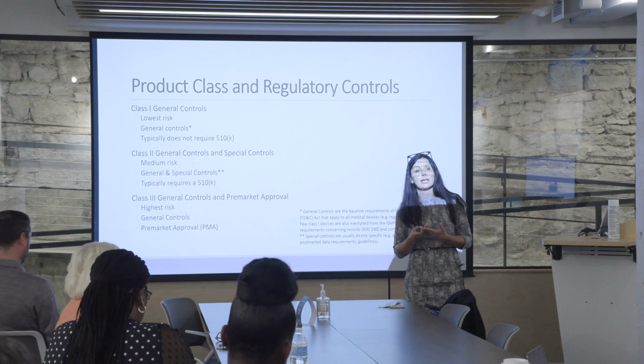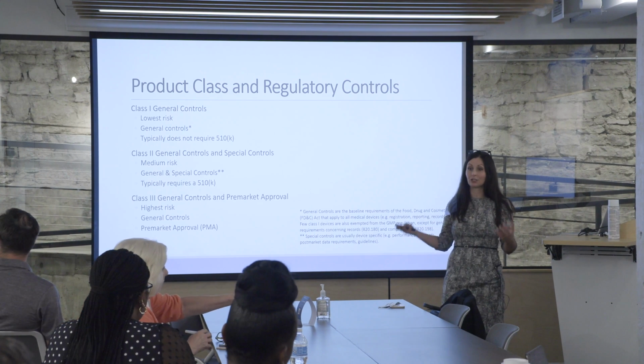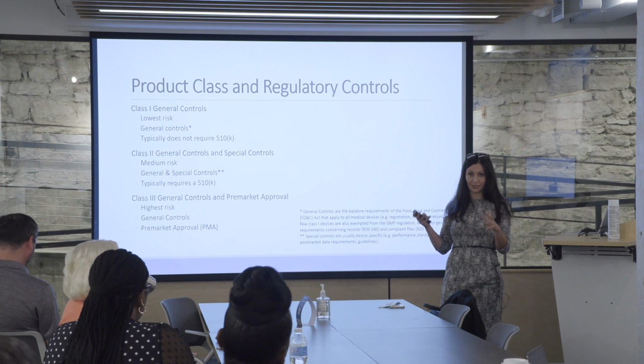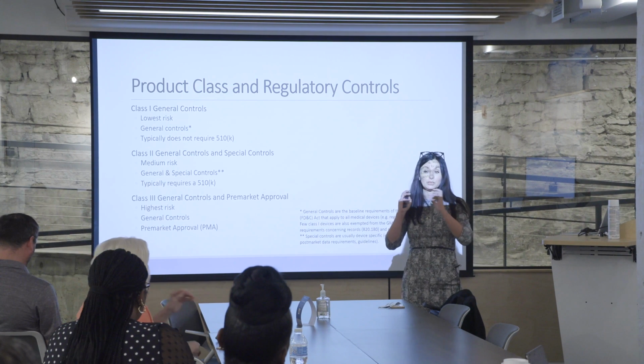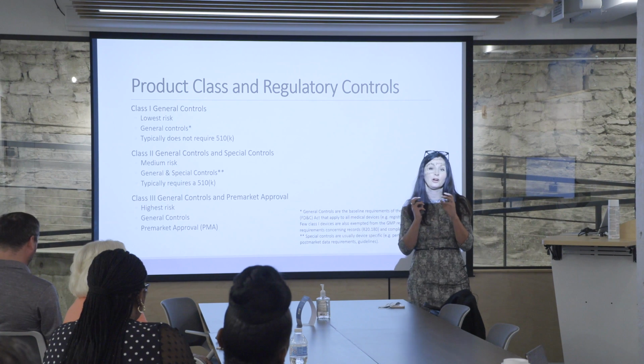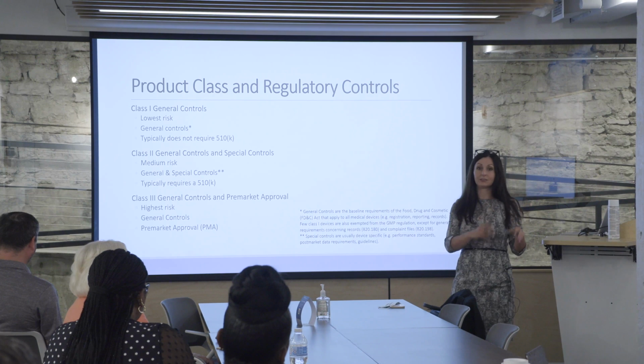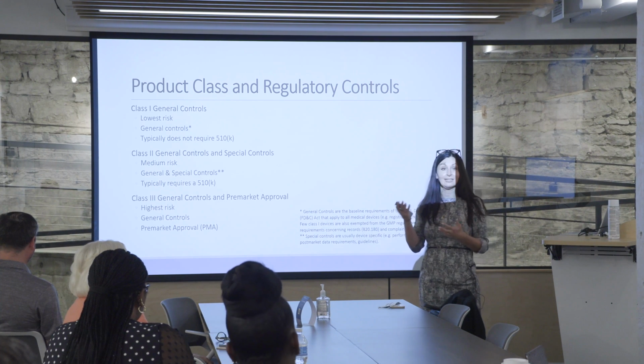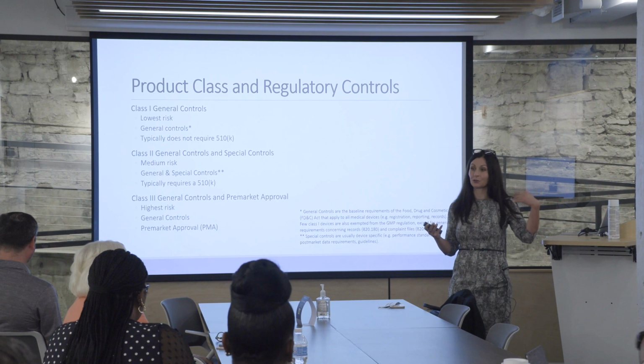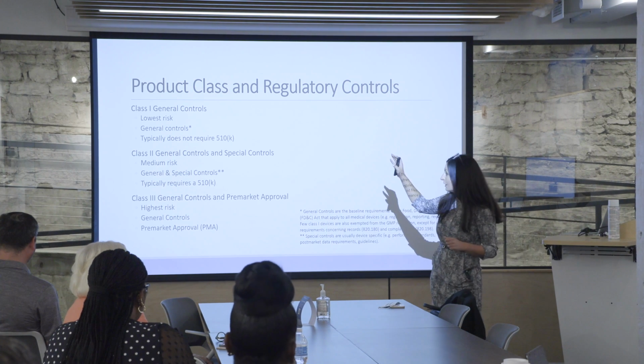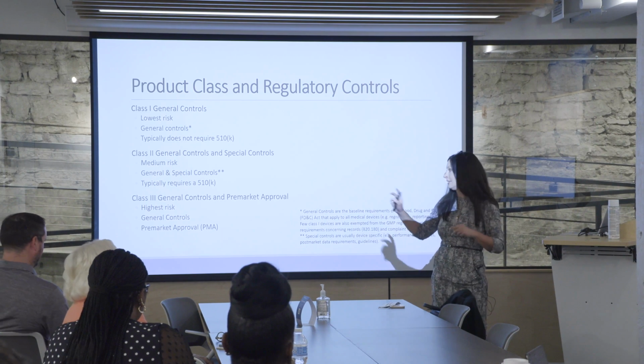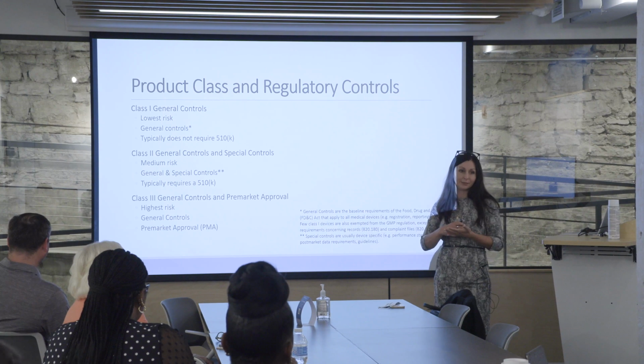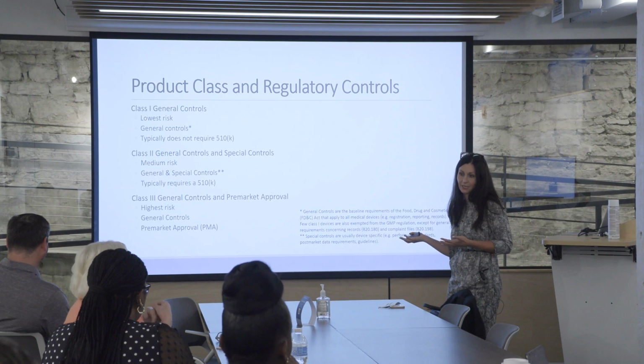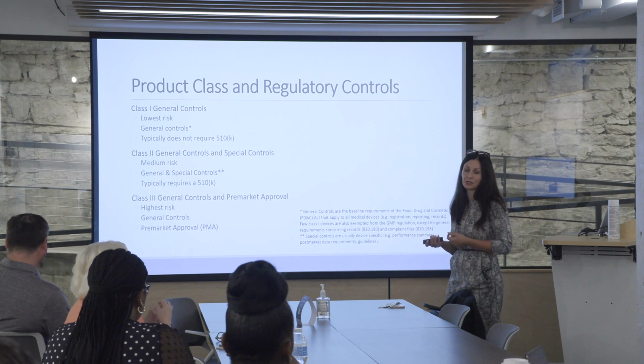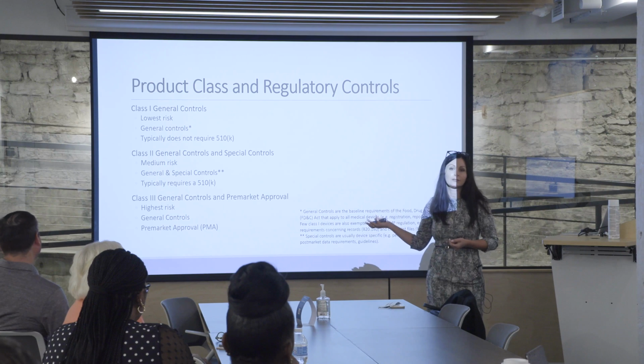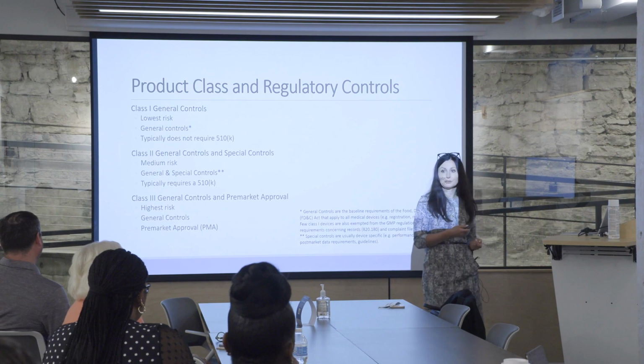But the standard there that you're looking at when you're submitting a 510K is a standard of substantial equivalence. So in that case, rather than proving that your product is safe and effective, which would require large-scale clinical trials, you are demonstrating that your product is substantially equivalent to a legally marketed device. So basically it's saying it's as safe and effective as this other product or these other products that are on the market. As you can imagine, 510Ks are easier than PMAs in that the burden is typically lower, right? If you do need a clinical trial for a 510K, which is still relatively rare, it's becoming more common, but it's still not the norm, it looks a lot different than a PMA clinical trial, which would be very large.